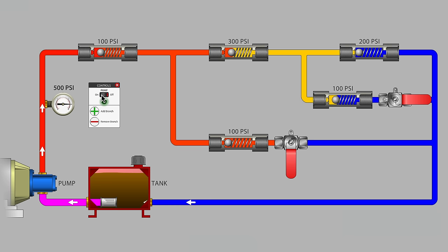Aha! 500 PSI. Congratulations to you, if you got that right. Our new path of least resistance, given the closed shutoff valve, is through the 100 PSI check valve, then this 300, then this 100. We add those three resistances together to find out that our system pressure is expected at 500 PSI. Alright, you're getting the hang of it.